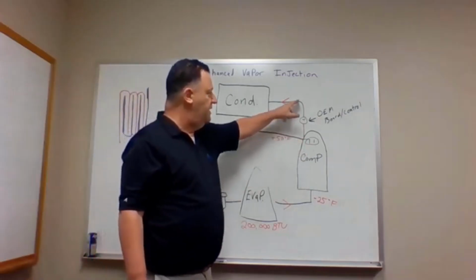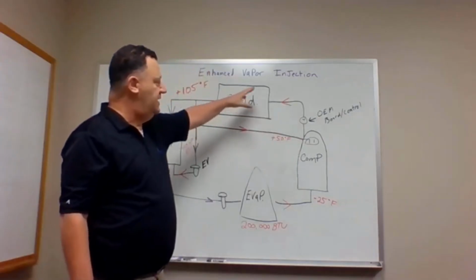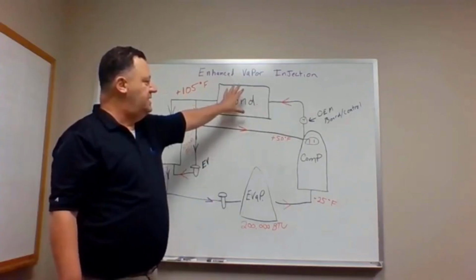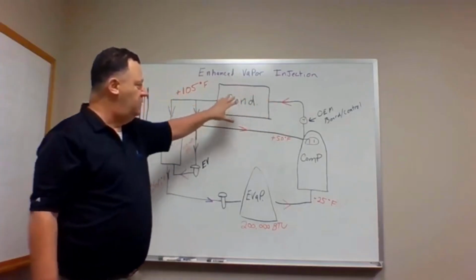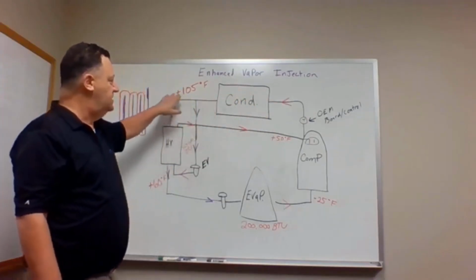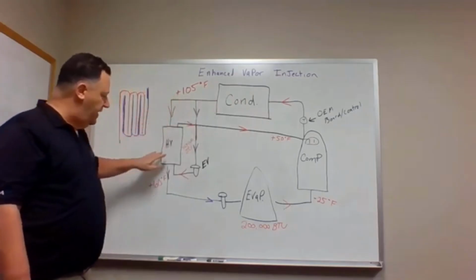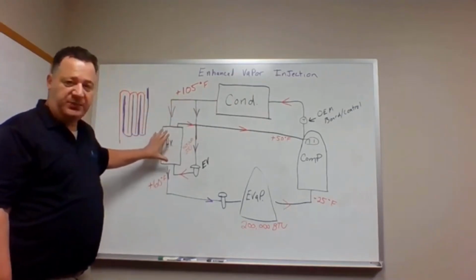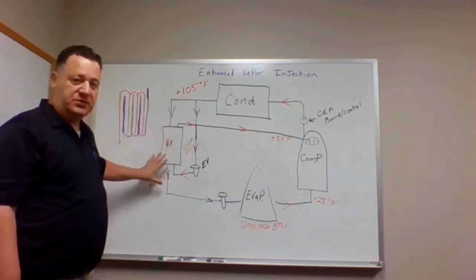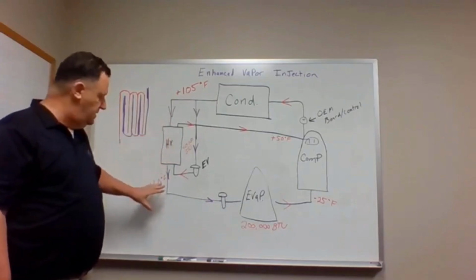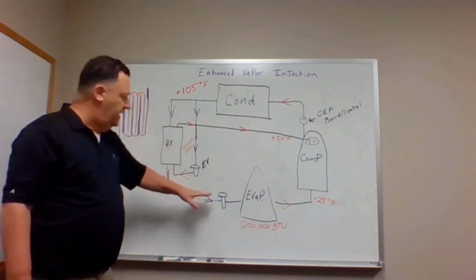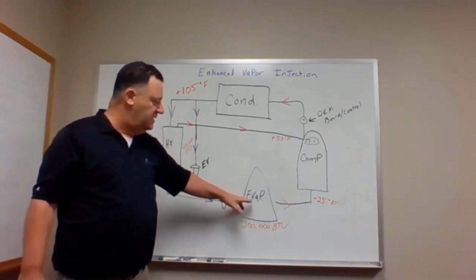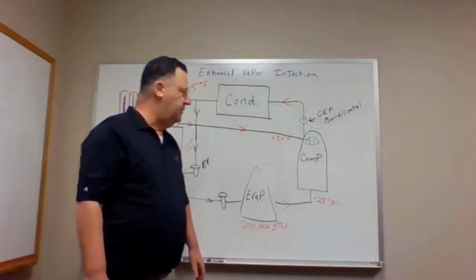We're coming out of the compressor, going into the condenser, rejecting heat, as we know. We're condensing the vapor into a liquid, okay? So we're coming out as a subcooled liquid, coming down through here. Now we're going to come through this braze plate heat exchanger, but it's not going to alter anything, okay? It's business as usual. And back to the metering device, through the evaporator, and going to the compressor, okay?